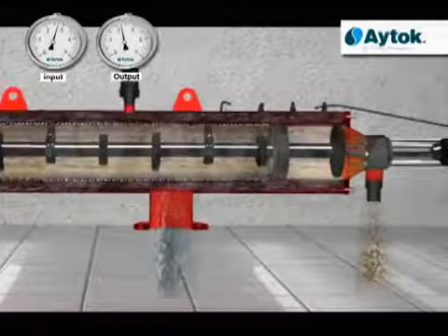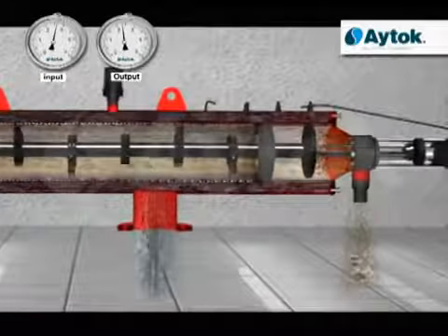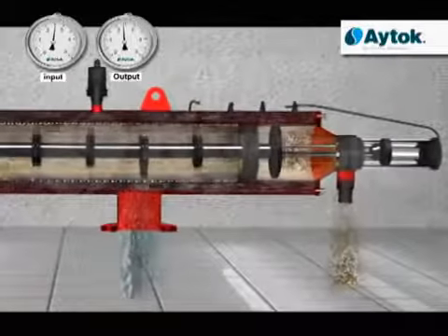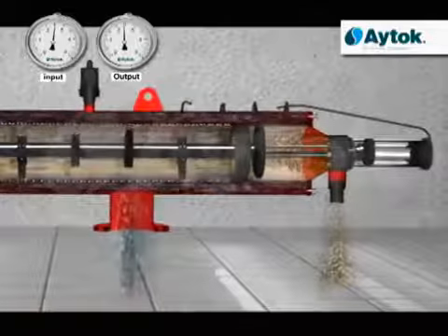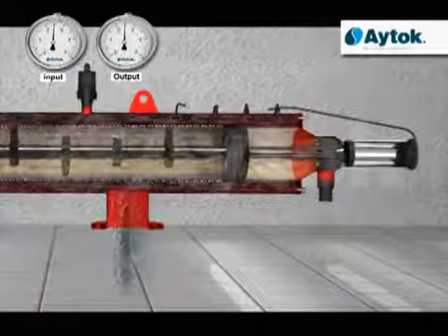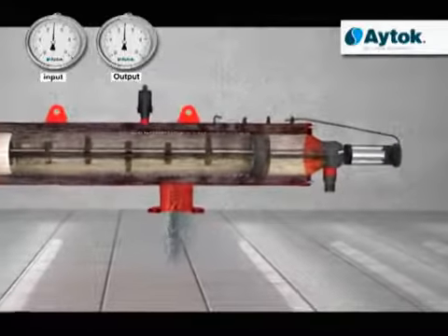appearing from the drainage unit. The circular movement that this action constitutes vacuums all dirt on the inner surface of the fine sieve with the nozzles. When this operation is finished, the cleaning collector makes a new backwashing operation and goes back to its former position, and the cleaning operation is completed. Filtration operation continues without any break during the cleaning operation.